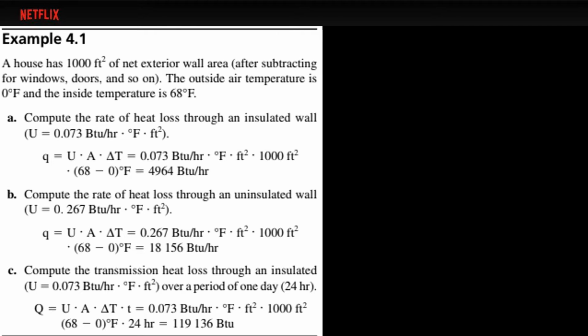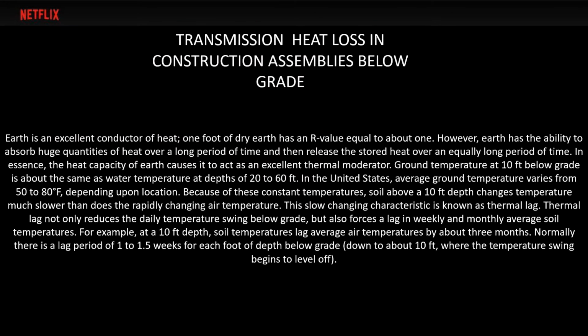Compute the rate of heat loss through the uninsulated wall. So our U is 0.267 BTU per hour. Using the formula from earlier, the answer we get is 18,156 BTU per hour. For C, compute the transmission heat loss through an insulated wall over a day. U is equal to 0.073 BTU per hour Fahrenheit feet squared, over a period of 1 day, 24 hours. Using the formula from earlier, the answer we get is 119,136 BTU.